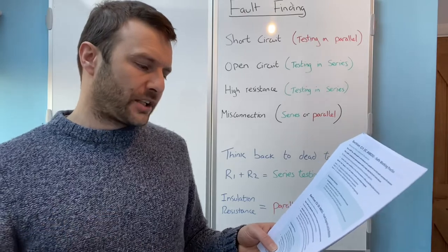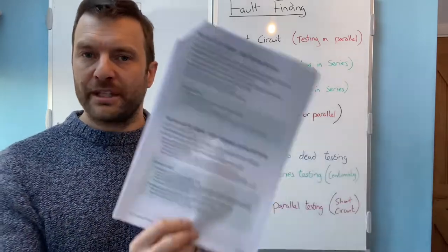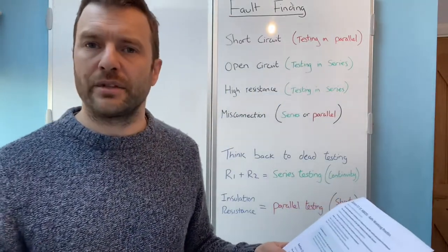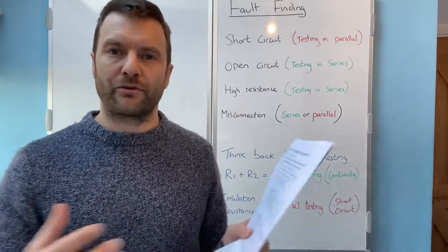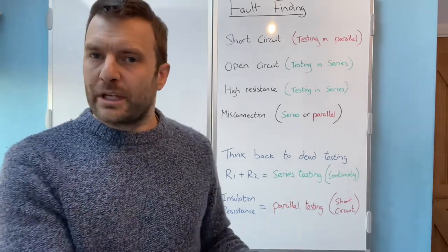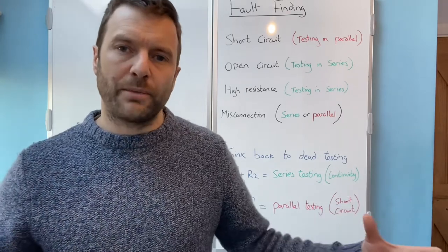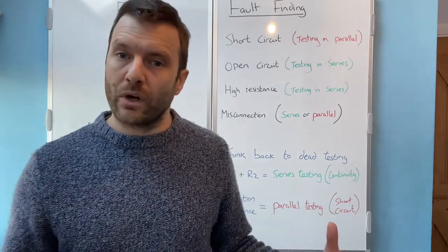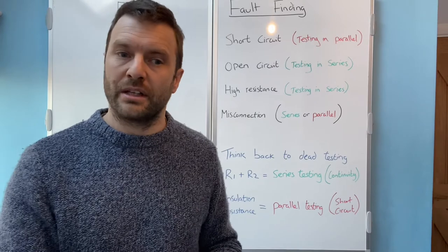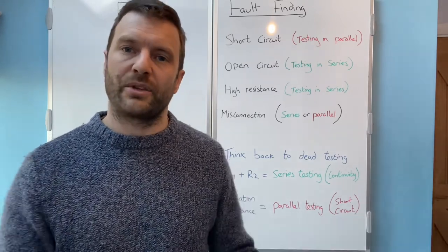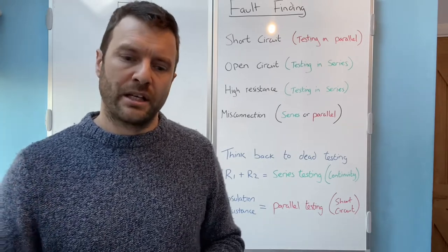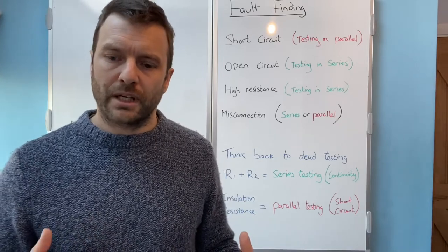Also, how would you check that your repair was successful? This is what I'm reading straight out of here. Reading between the lines, I would say that what NET are telling you there is that most people forget that once they've done the repair, we then need to retest. Now, obviously, if you've just tightened up connections, then it would be just retest connections. If you run a new length of cable, then that could involve a minor works certificate and some testing, R1+R2 testing, insulation resistance testing, and possibly even RCD testing, depending on the type of circuit that you're working on. I don't think they give you a lot of space to write all this in, so you've got to be realistic. But those are the kinds of things that you need to think about, okay?